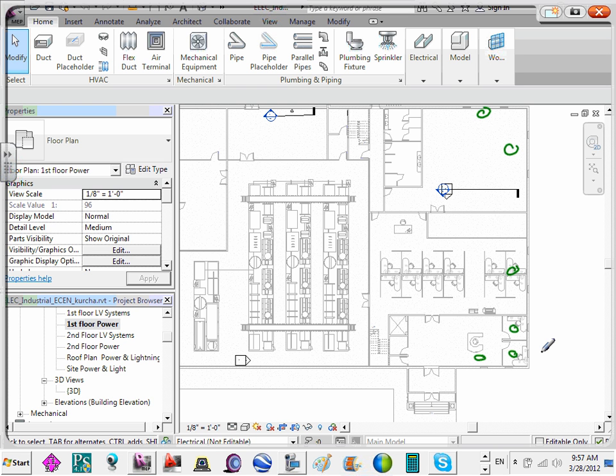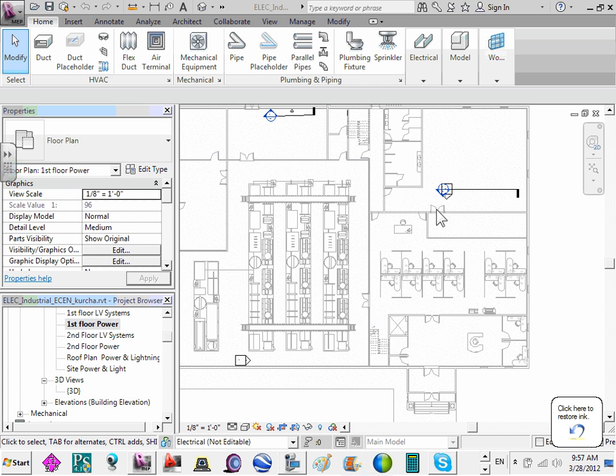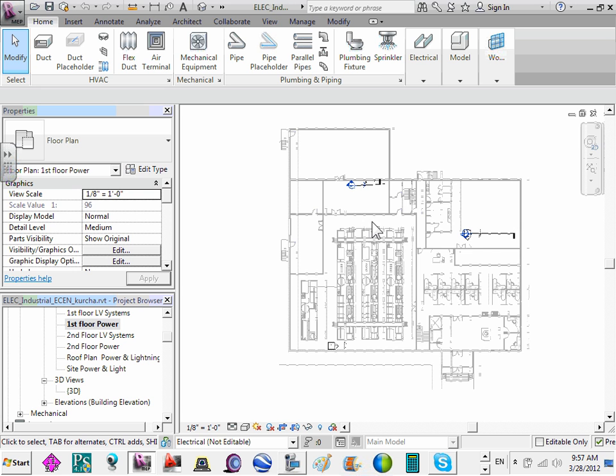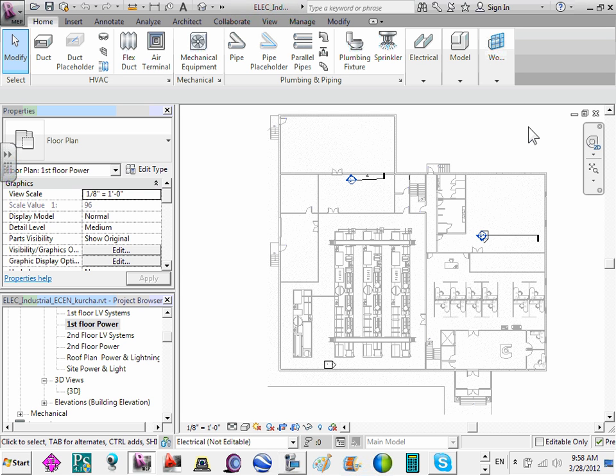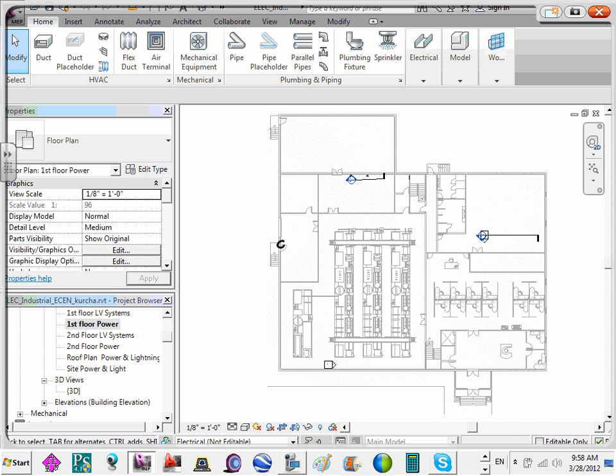If they want to have one in the main atrium area, they can. But you're also going to have your door contacts. The door contacts are going to go at each door exiting the building. That's just a little magnetic piece that sits up there, monitored by the security system you're going to put in your electrical room. And again, here you're going to have door contacts on each exiting door up in the front area.